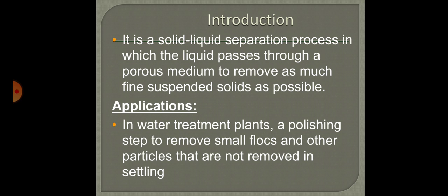Like I told you, it is a very important operation, and it is actually used to remove various particles like the fine flock particles, the color, dissolved minerals and microorganisms that are present in water. In the filtration process, the water is allowed to pass through a medium which we call the filter medium. Usually we take sand as a filter medium. There are other alternatives to sand also, like gravel, anthracite, etc. So sand is a filter medium, and we allow water to pass through it.